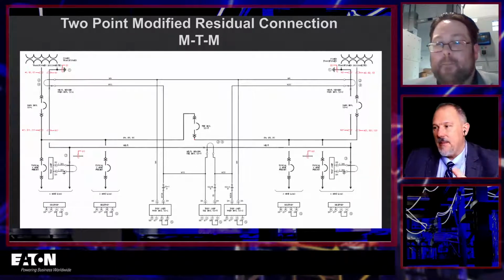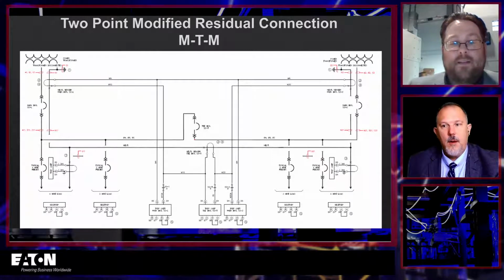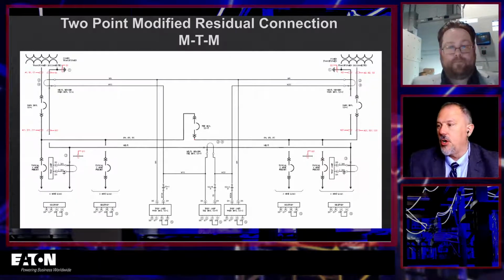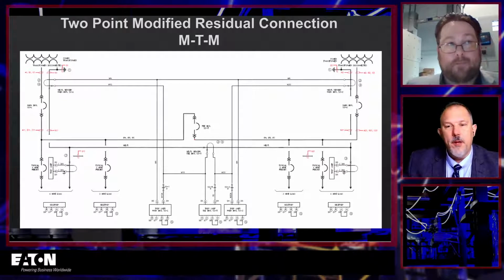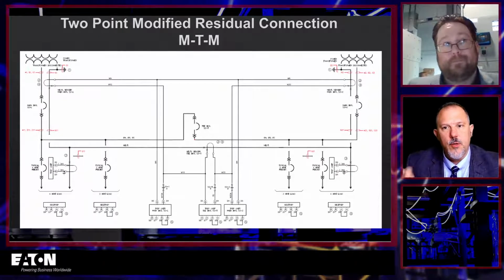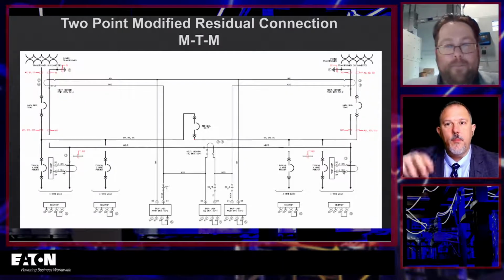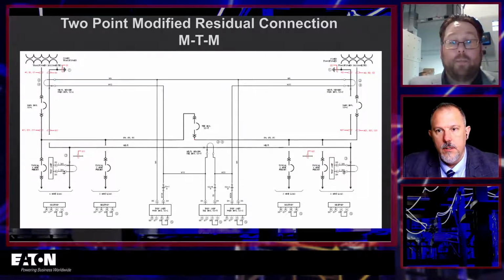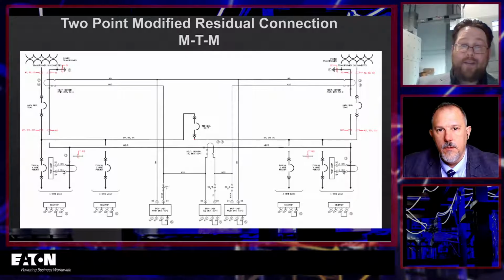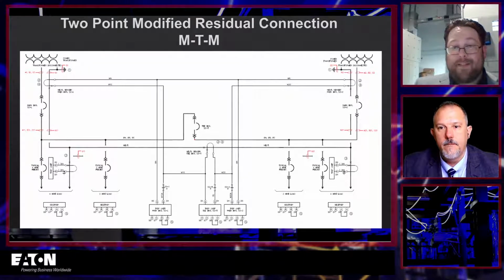So in main-tie-main situations, you've got to be careful about what you're going to open up. Are you going to open up all your feeder breakers? Are you going to open up the tie breaker? Are you going to keep it closed? Or do you have to do one test with it open and one with it closed? Well, that's exactly what you're going to do. You're going to run tests with your two mains closed and your ties open. You're going to run tests with one main and the tie, and then test with your other main and your tie, because you want to confirm.